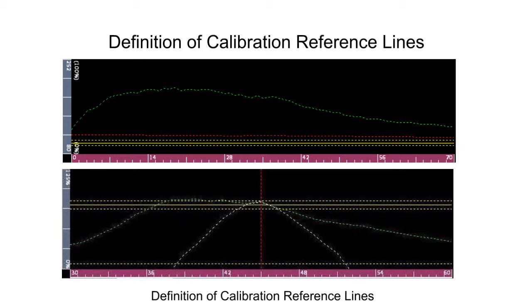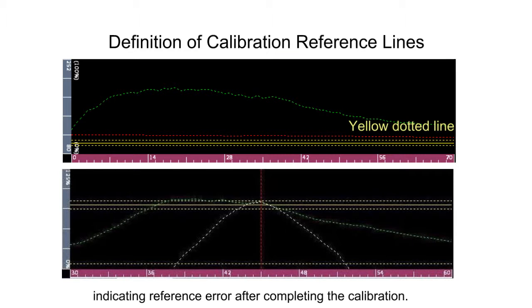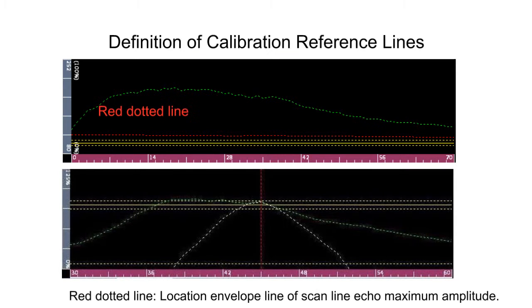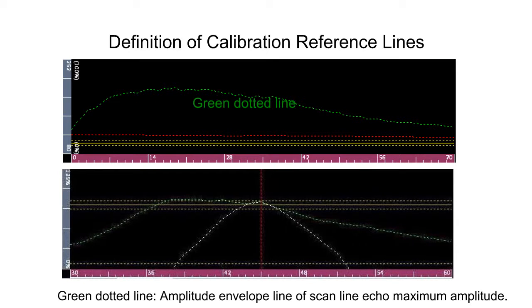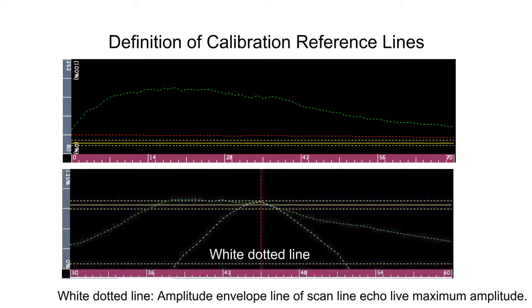Definition of calibration reference lines. Yellow dotted line, reference error line, indicating reference error after completing the calibration. Red dotted line, location envelope line of scan line echo maximum amplitude. Green dotted line, amplitude envelope line of scan line echo maximum amplitude. White dotted line, amplitude envelope line of scan line echo live maximum amplitude.